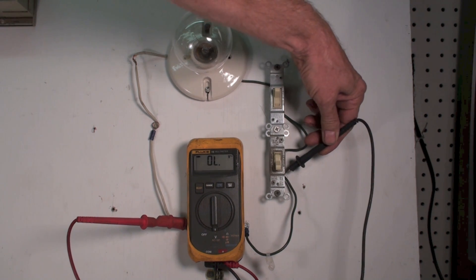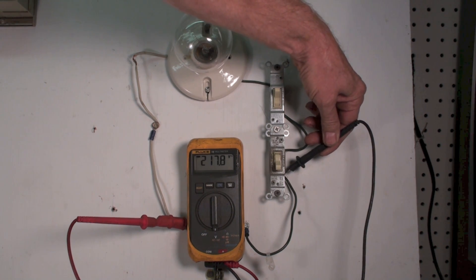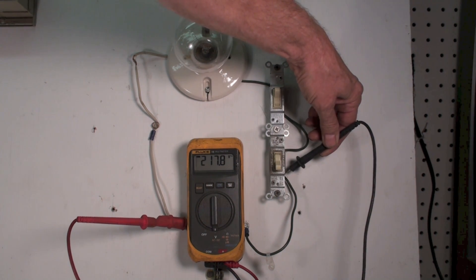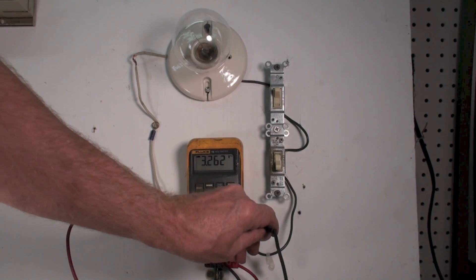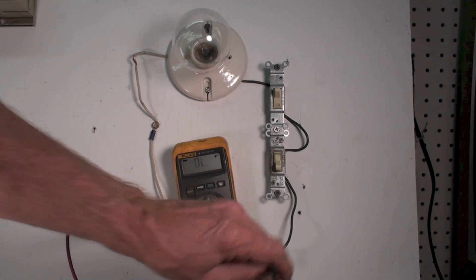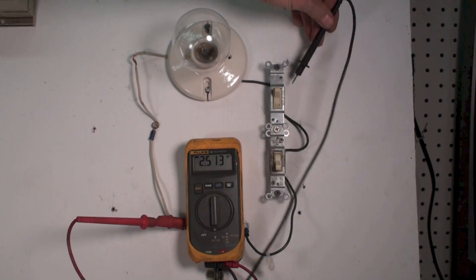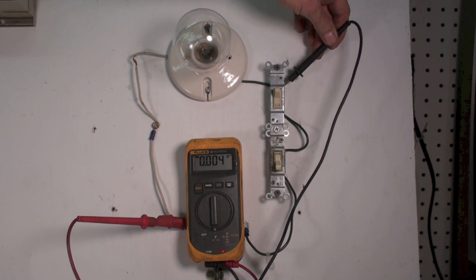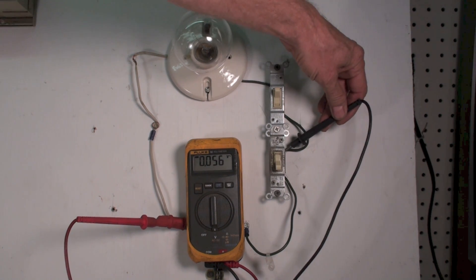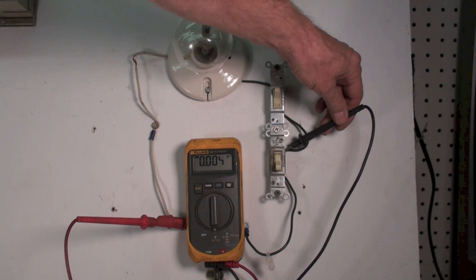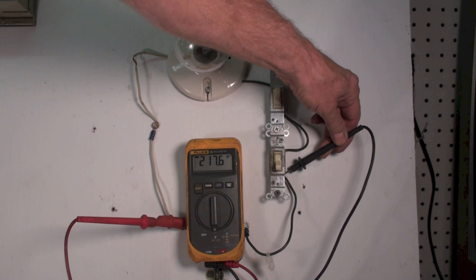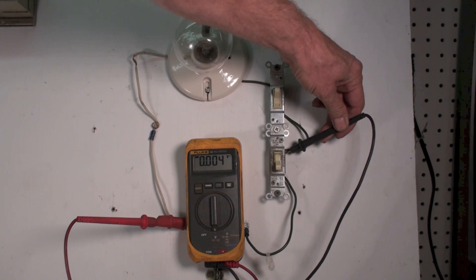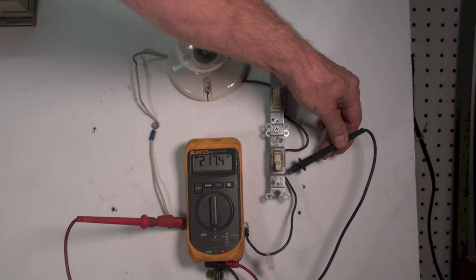I go here, still don't see voltage. And I go here and I see voltage. Okay, by the hopscotch method I have first went to here to find out if there's power available. Then I went up here to find out there's power to the load. And then I started hopscotching down the switches.